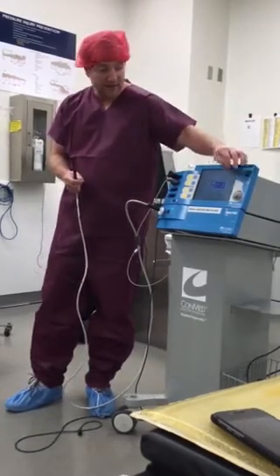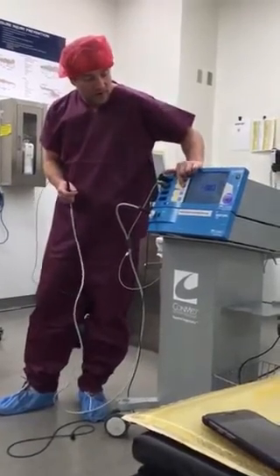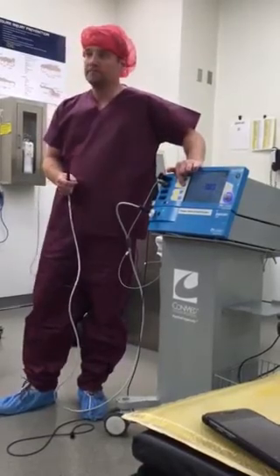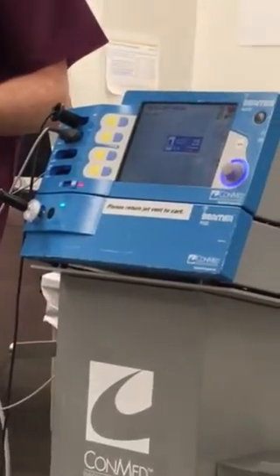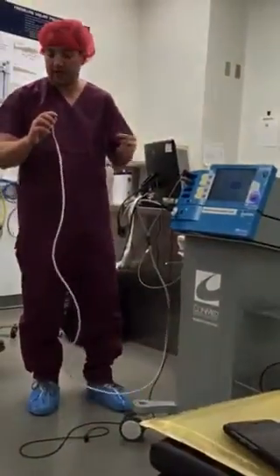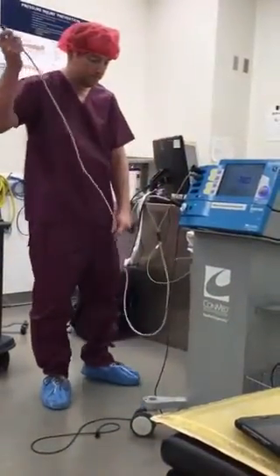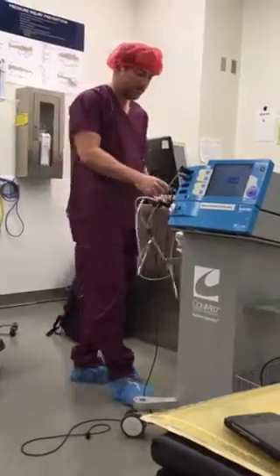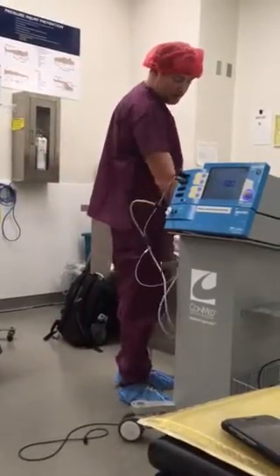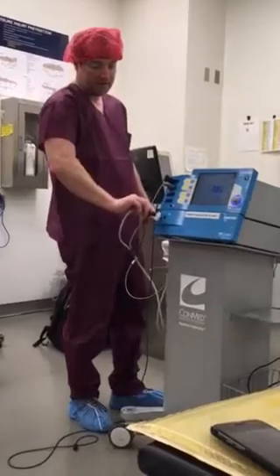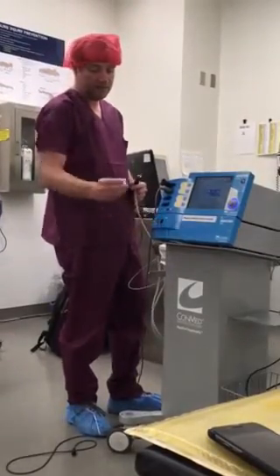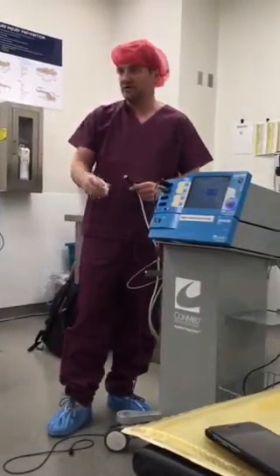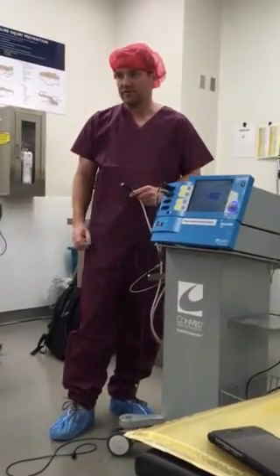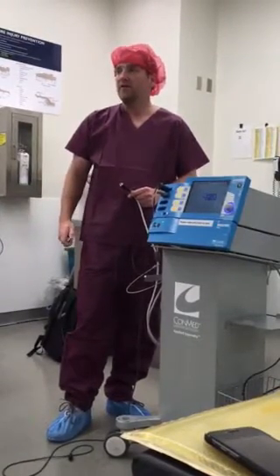Just like the other settings on here, you have your wattage, and then you have your flow rate. These can be adjusted accordingly based on what the physician wants to do. When you're done with this, you just pull this off. This is disposable. This you can just wipe down, just like you would the monopolar active cord, and you're done. In each box of probes, there's enough of these filters for every procedure, so these can be taken off. You can throw them away after every procedure and put a new one on. Those come with the probe? Yeah, they're in the box with the probes.